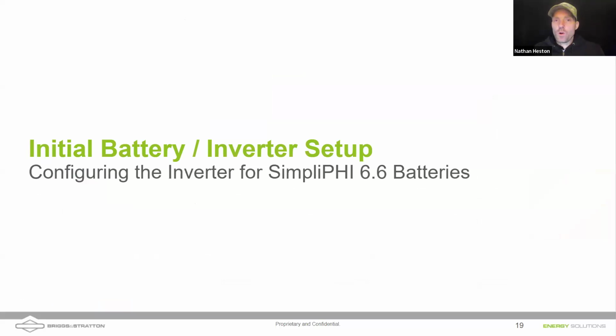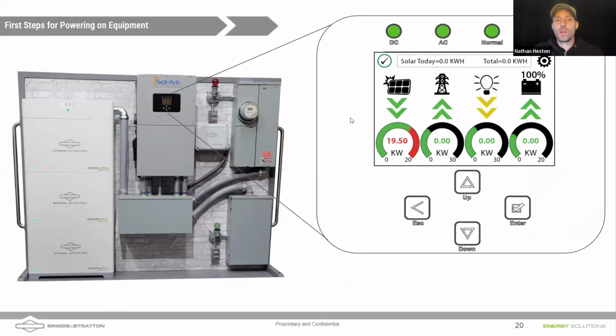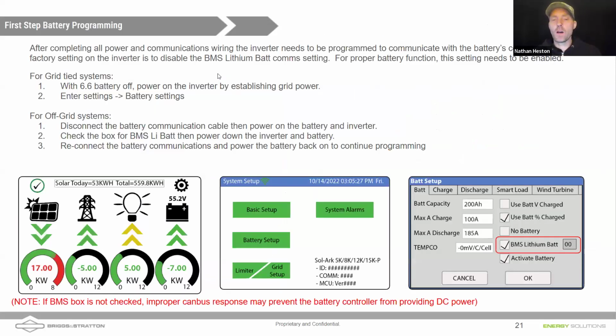So we'll jump into the programming here. Daniel, interrupt at any time with questions, but on the initial setup of the battery, we do have to make sure that the inverter knows to expect a communicating battery. The default on a Sol-Ark inverter is to not have the communicating battery box checked. And because of that, it's not sending the appropriate signals on the CAN bus channel. And so you will see a screen like this on the front of your Sol-Ark. And when we first power that Sol-Ark on, we're going to try to use a different source other than the batteries. If you don't have a different source other than the batteries, we'll just disable communications by unplugging the comms cable from the battery. And I'll explain why here.